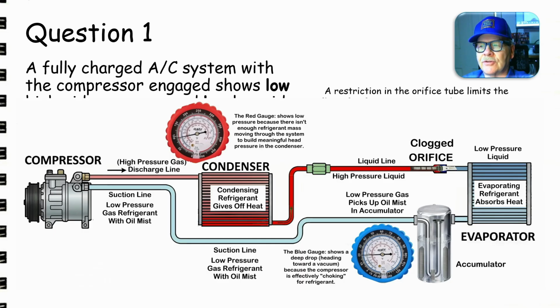Now this is a close-up design, you can look at that. Notice how you've got high pressure gas coming out here, it condenses, gives off heat, the refrigerant that you picked up over here. Wait a minute, let me get my laser turned on. Discharge, this is where you're going to be measuring your high side pressure. I've built this illustration just for this PowerPoint presentation, so y'all feel privileged, okay? You won't see this anywhere else online unless I posted it there, or maybe you see it on carparts.com or OBD Advisor, because I review for those two outfits.